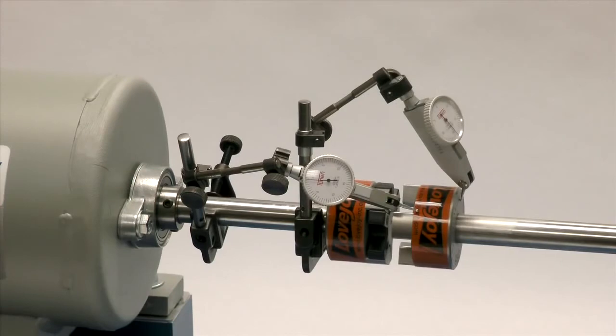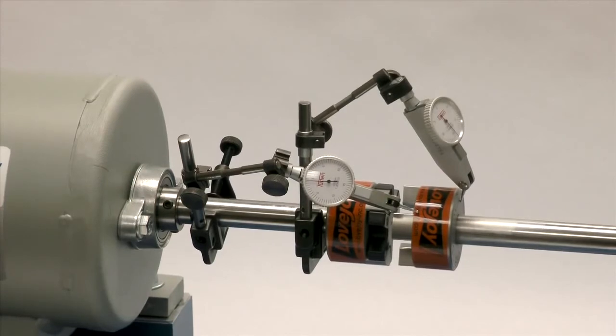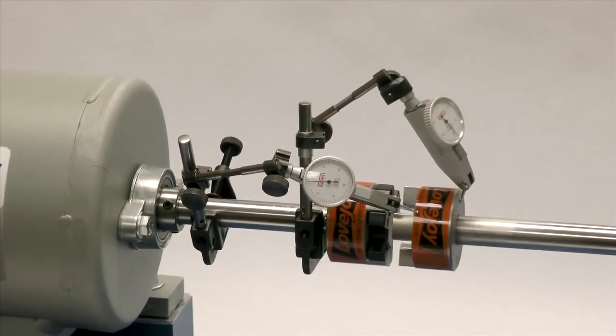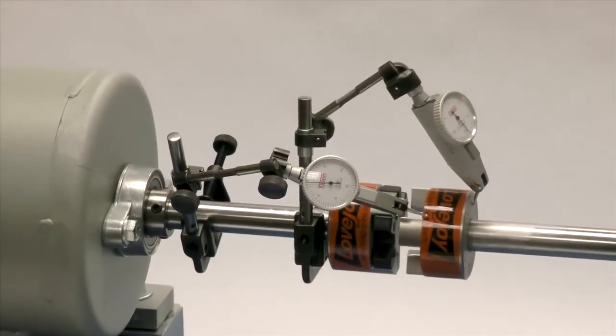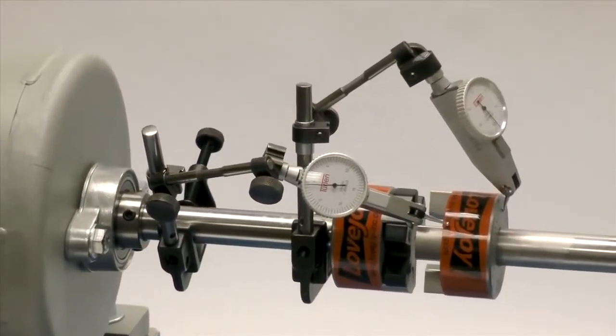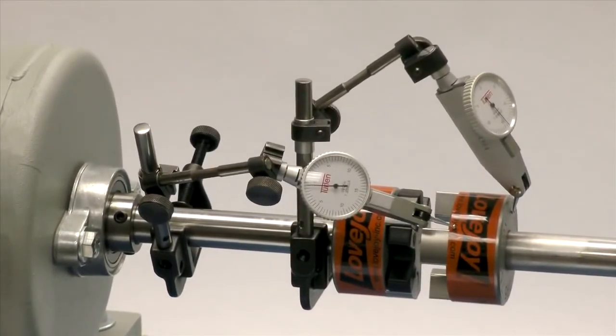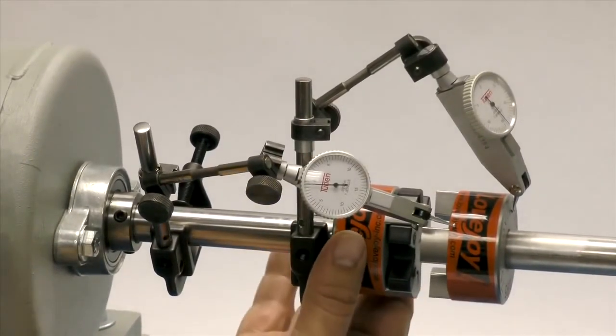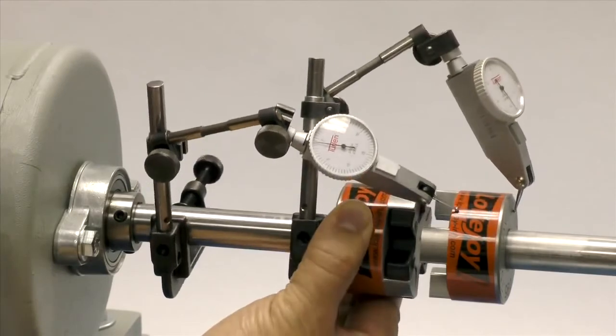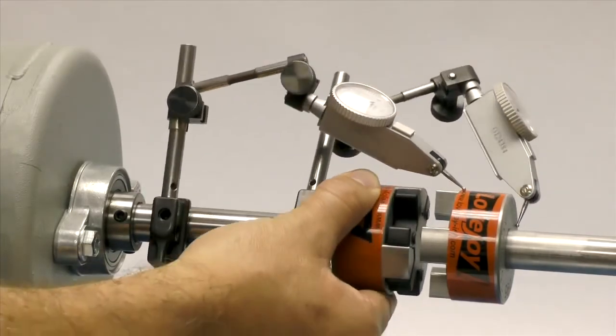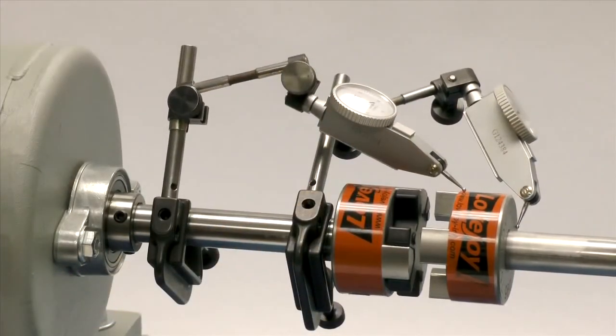If using a dial indicator, mount the indicator on the driver shaft with the sensor touching the hub on the opposite shaft. Rotate the shaft with the indicator to the 3 o'clock, 6 o'clock, 9 o'clock, and 12 o'clock positions, and make notes of the deviation on the dial. If this exceeds .015 or 15 thousandths of an inch, adjust the equipment to correct this condition.